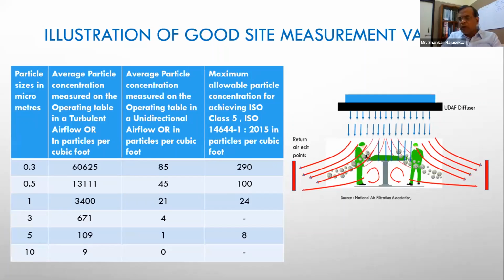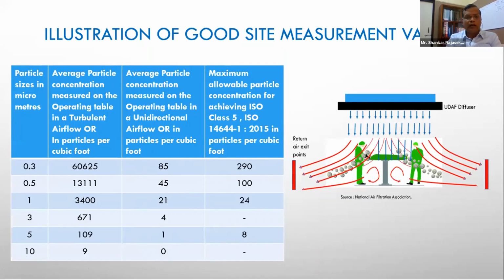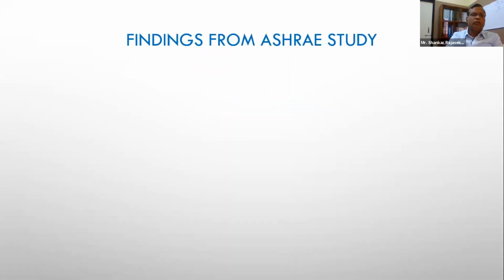The NABH talks about particle concentrations on the supply air grill and not on the table. But the critical area is on the operating table. And if you look at that, in a good OR with unidirectional airflow, this is the kind of particle concentrations that you will get for every cubic foot. And this is the allowed limit as per the standard. And this is what you will get in a turbulently ventilated OR. A good turbulently ventilated OR, I'm saying. So you can look at the benefits of using a unidirectional airflow system. But if it is not installed and tested correctly, it creates more harm than good, which we will be seeing.